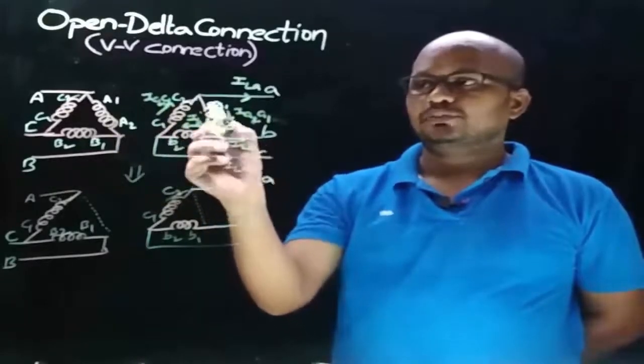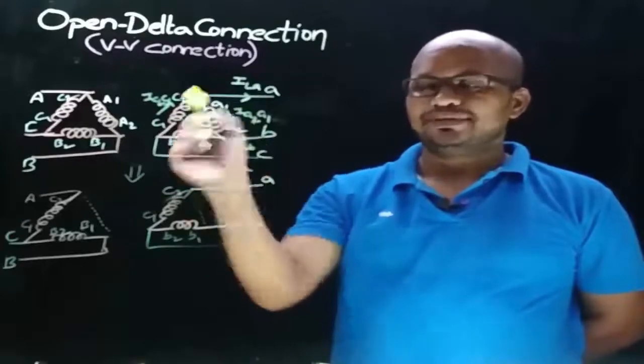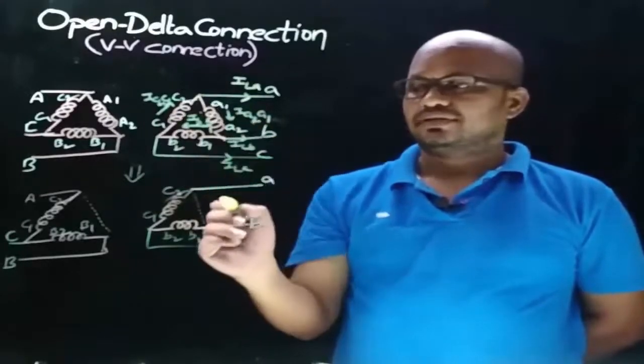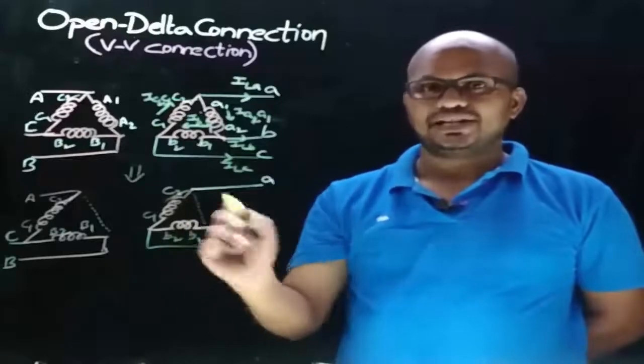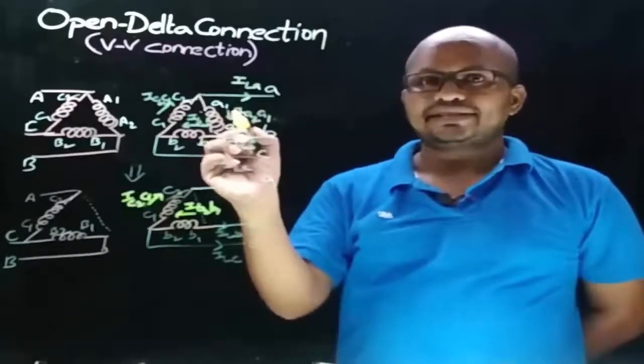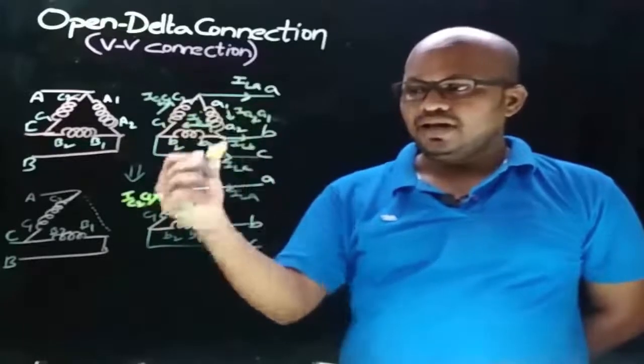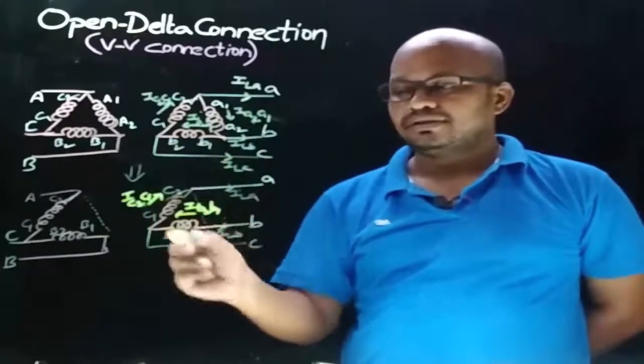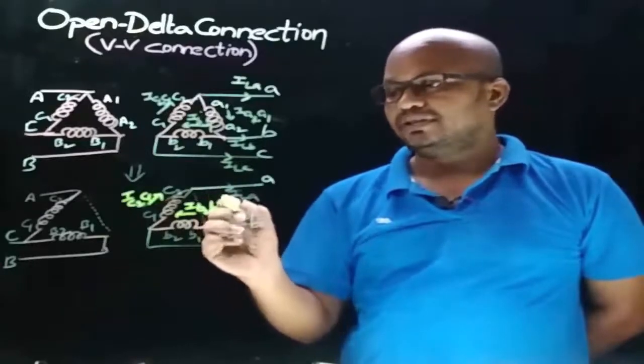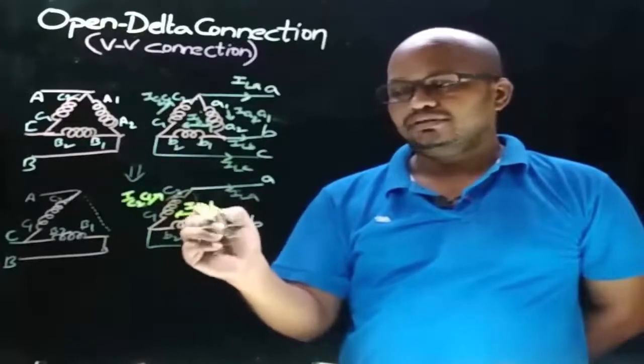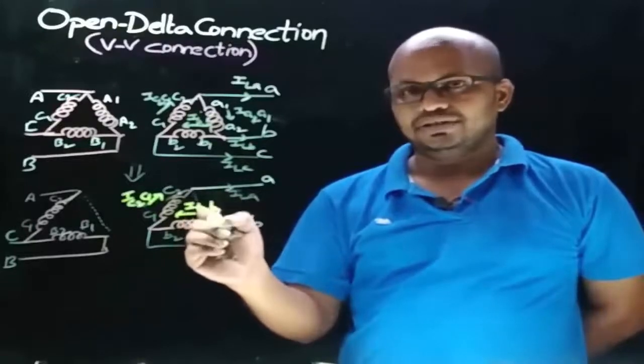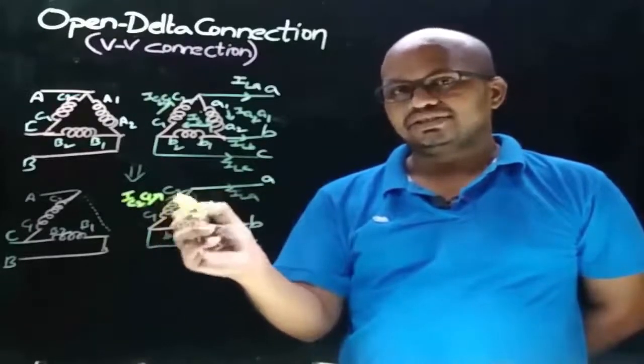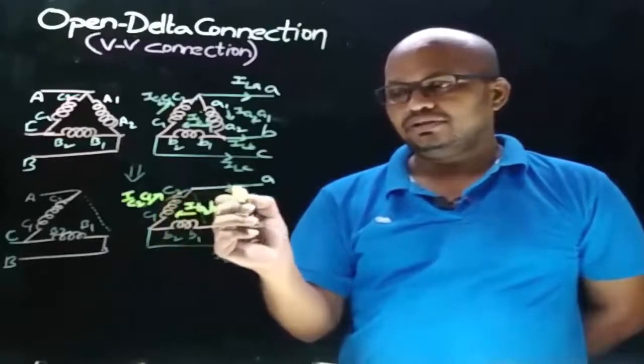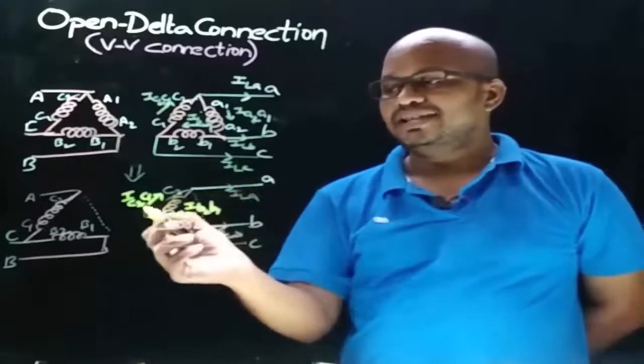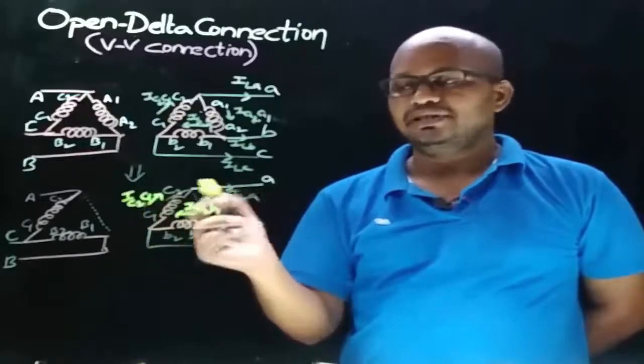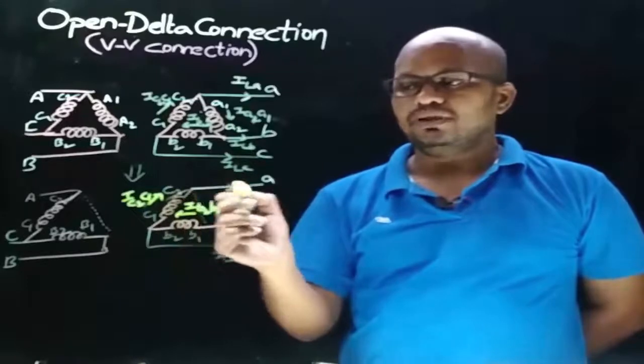So for that, we removed the small a1, small a2 winding from the secondary winding connections. So this is the resultant secondary winding connection. After removing the transformer 1 secondary winding from this delta connection, observe the currents in the resultant winding connection. Observe that after removing the transformer 1 secondary winding, this phase current directly passes through the line, meaning IC to C1 is equal to ILA, meaning this phase current is equal to line current.